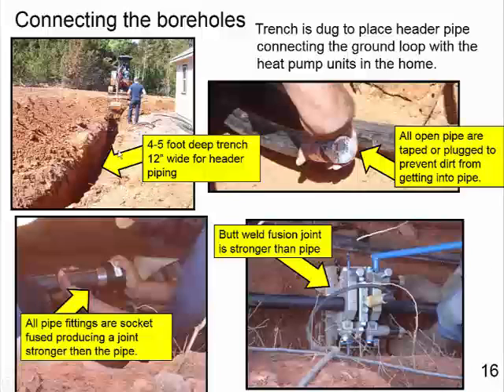In connecting the boreholes, a trench, in this case 4 to 5 feet deep and 12 inches wide, is dug for the header pipe. All the header pipe ends were taped and plugged to prevent dirt from getting into them. Here you see some of the socket welding going on, and the socket joints are usually stronger than the pipe itself. And here you see some of the butt joints to put the pipe together. The joints are considered to be stronger than the pipe itself because they're all fused together. There's no mechanical fastening underground in this particular instance.